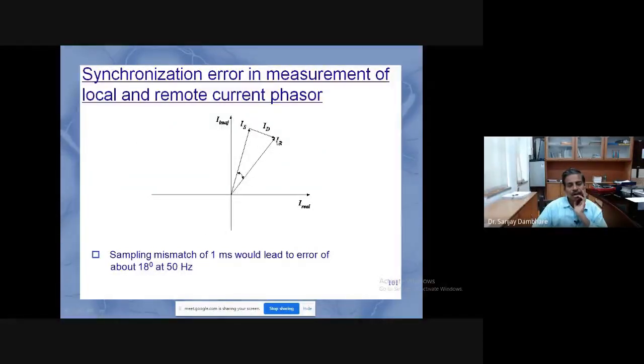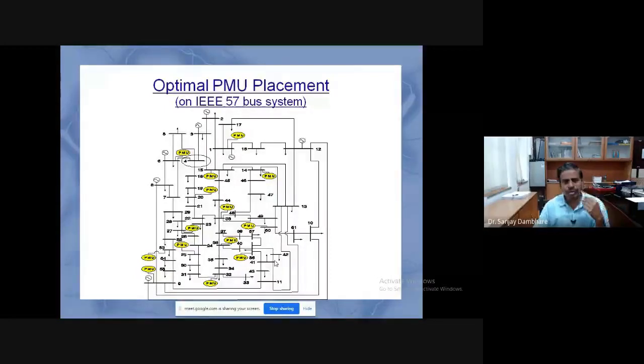So IS and IR are the current signals, and IS and IR have a mismatch of 1 millisecond. Although they have the same magnitude, because of their phase difference, this ID will flow, right? This is a differential current which is caused by the sampling mismatch and not because of the actual current mismatch. Yeah, so this slide is showing where to put the PMUs.